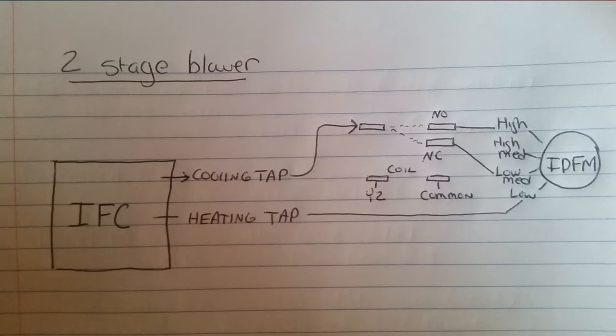We can see that the two taps go over. One goes directly to the indoor fan motor, the heating tap on low. The other one's going to go to a relay that we're going to install. Typically a 9340 relay is what I like to use, nice and reliable. Tested over time. It's been around for a long, long time. We'll have a coil on the bottom of it that has a Y2 and a common to energize the coil.